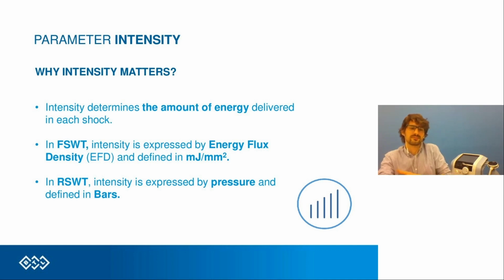one, the radial shockwave, is using bars as a unit because, as I mentioned, the pressurized air is inside of the device. That's why we are counting bars. We are measuring how much the air inside of the device is pressurized. Where it comes to the focused shockwave, we are talking about energy flux density, which is specified by millijoules per millimeter square. We are not talking about the inner aspects of the device, but about the energy of the shockwave outside. This is usually measured by optical hydrophones.